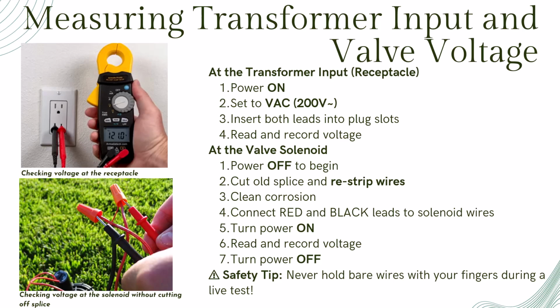For transformer input, measure power at the wall receptacle or junction box. Push both meter leads into the plug slots. This ensures proper contact even in tamper-resistant outlets.